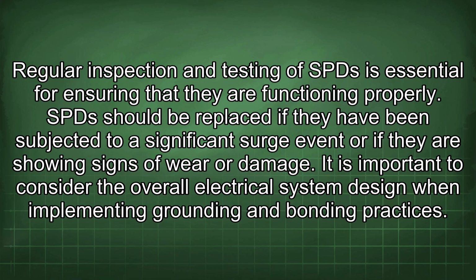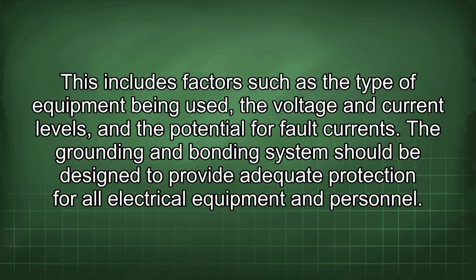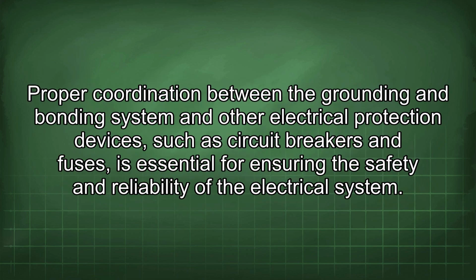of wear or damage. It is important to consider the overall electrical system design when implementing grounding and bonding practices. This includes factors such as the type of equipment being used, the voltage and current levels, and the potential for fault currents. The grounding and bonding system should be designed to provide adequate protection for all electrical equipment and personnel. Proper coordination between the grounding and bonding system and other electrical protection devices, such as circuit breakers and fuses, is essential for ensuring the safety and reliability of the electrical system.